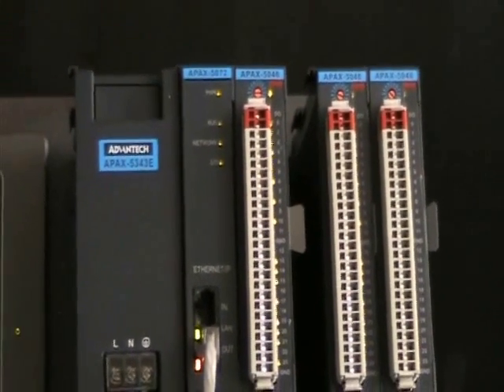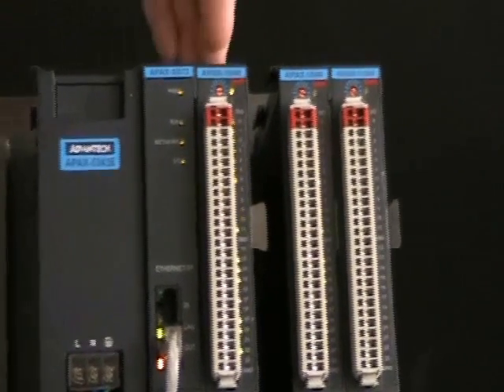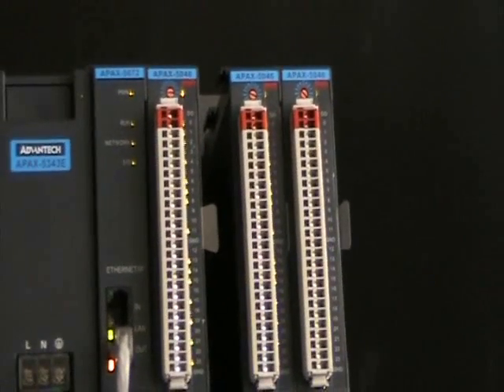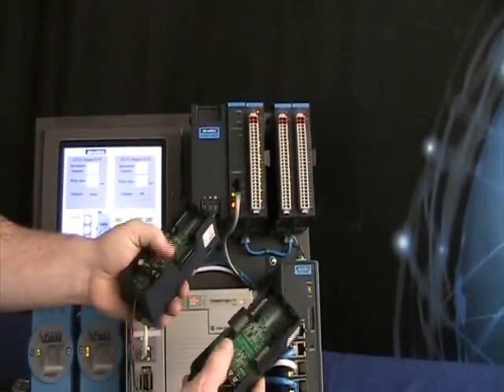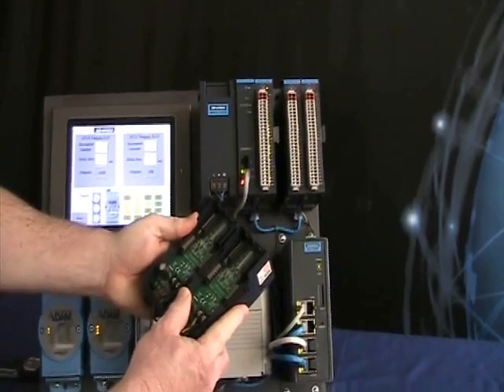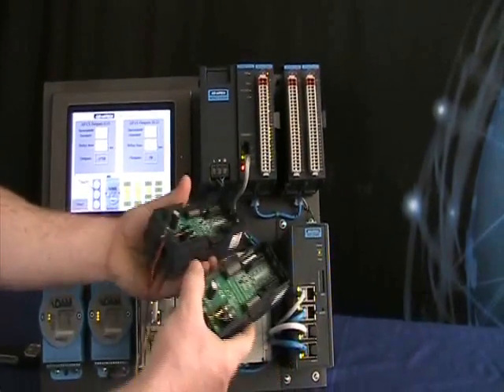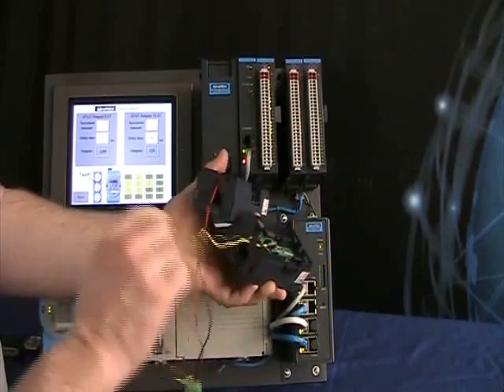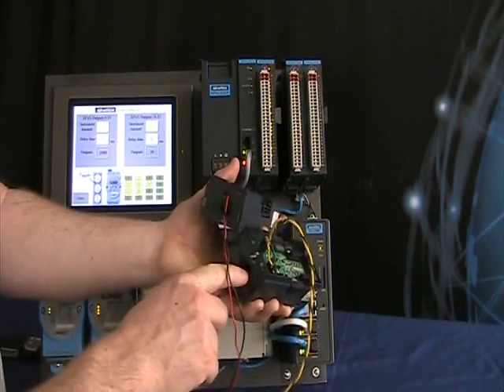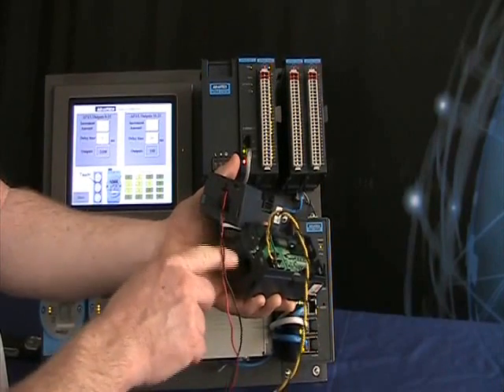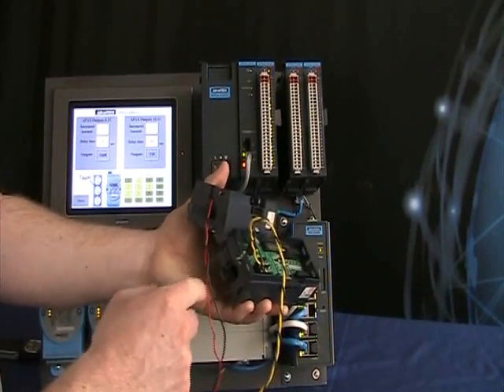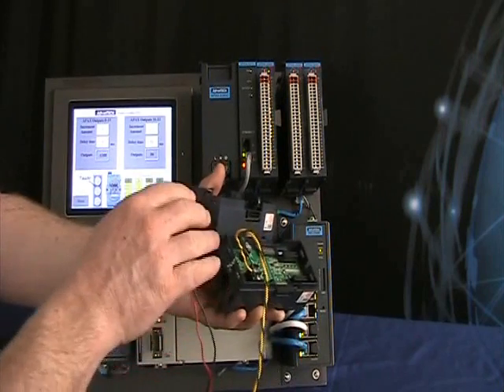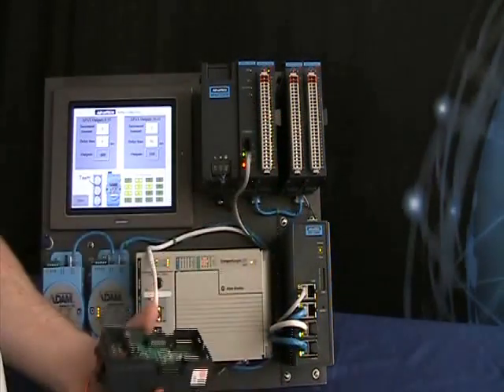Now the APAX product line can be connected on a backplane, and here I have a sample of the backplane. As you can see they just plug together. There's two slots each. They can be together or separated, and if they're separated then at the bottom they have Ethernet ports right here. This Ethernet communication is a proprietary communication and it's high speed, and it's just only to be used for the communication for the I.O. back to the coupler.